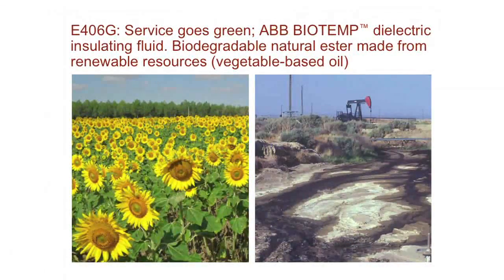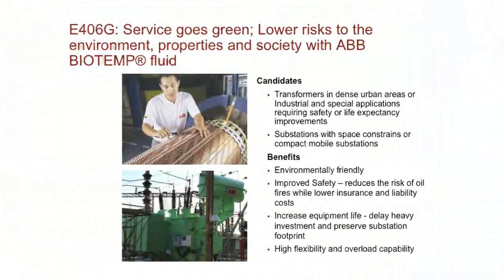The Biotemp retrofill option in the field allows us to come in, remove the existing oil, perform some flushing, and backfill with the Biotemp fluid. Another key option is if that is intended when the unit is going to the factory, we can look at the design parameters, the thermal parameters, the cooling parameters of your transformer, and redesign that transformer for a Biotemp fluid to ensure that we meet or exceed the nameplate or design value ratings of that transformer. And this just represents an oil refinery and a sunflower field, as the basis of the Biotemp fluid is a sunflower-based product.